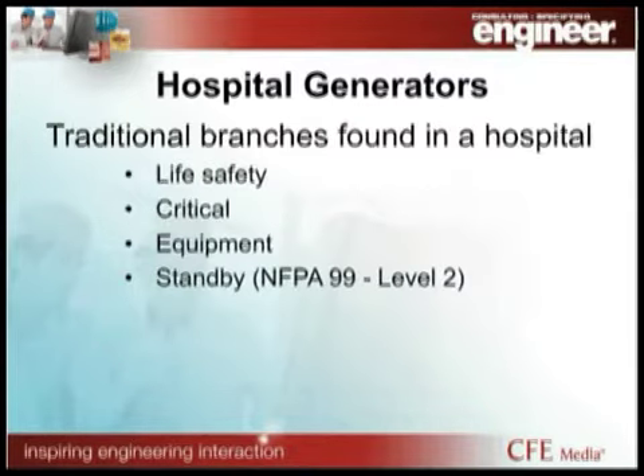What we are going to cover is how we take the information that we see in 517 on how to divide up our emergency essential systems into life safety and the critical, and then how we also address the equipment and the standby requirements for the facility. Standby, as defined by NFPA 99, is the level 2 non-life safety portion of the emergency system.